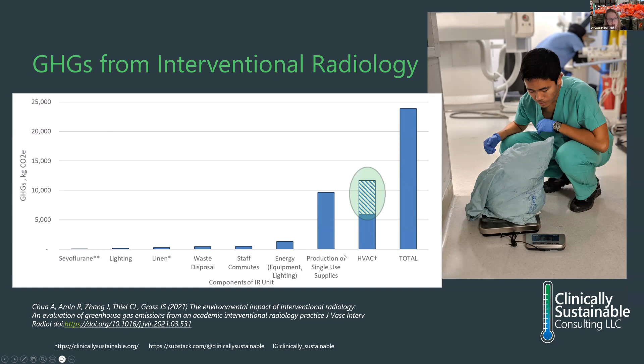So this was a major finding: just turn off the lights, turn down the air changes per hour so you're not ventilating or conditioning so much air for these spaces. Operating rooms have high airflow rates as required by code, but code also says that when you're not using them, you can reduce down to normal room ventilation rates, without such tight humidity and temperature controls. This supports that part of the code, showing we can reduce what we're using and still get real savings.